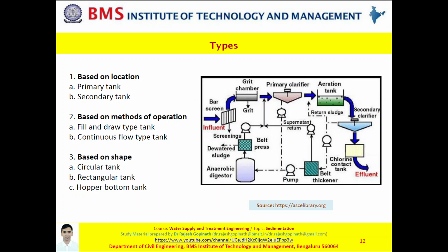So thereby primary sedimentation not only facilitates settling and sedimentation but also serves as an equalization or flow normalization basin. Secondary sedimentation tank is when this tank is present after certain other important operations and processes such as coagulation, aeration and so forth. Now basically the decision to have primary or secondary or the number of units depends on the situation, the demand and the extent of treatment which is required. But please note, it is merely based on where it is located that this classification is applicable. However, based on the location, it serves to perform more than one function.